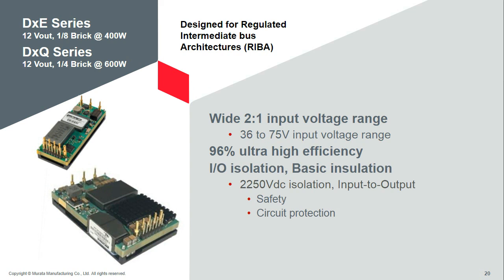Most systems in networking and telecom applications will require an isolated intermediate bus. This provides a measure of safety for a technician that may be working on the system. Let's say, for example, there's an input failure of that N+1 system. It was struck by lightning, and all of a sudden there's 150 volts at the input to the converter. Well, that 150 volts won't show up at the output of the converter, destroying your circuit or providing a safety issue for any technician or service personnel that might be working on the system.